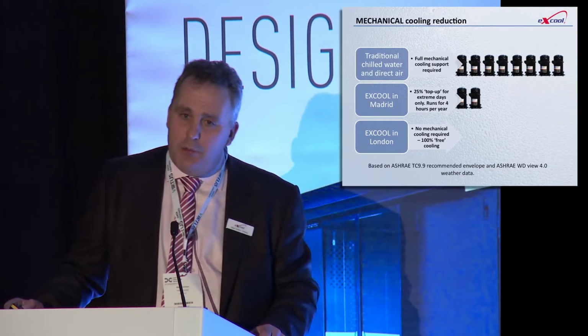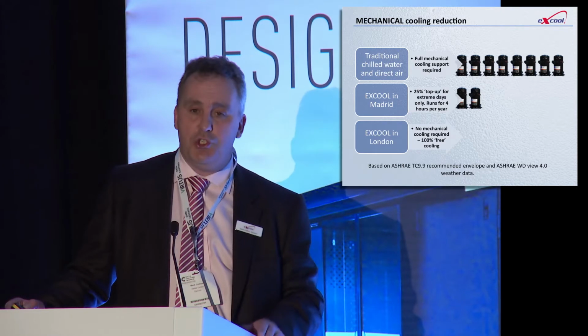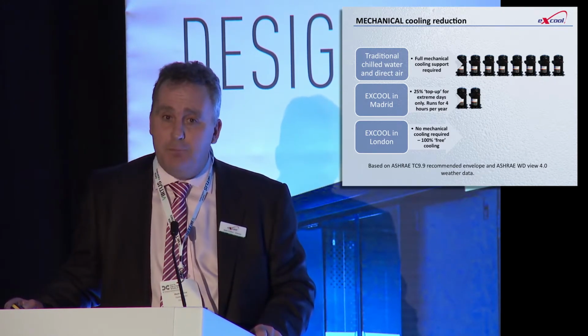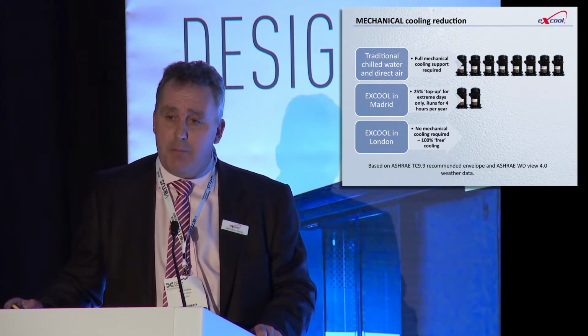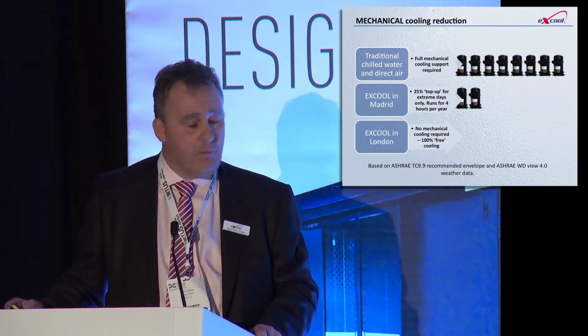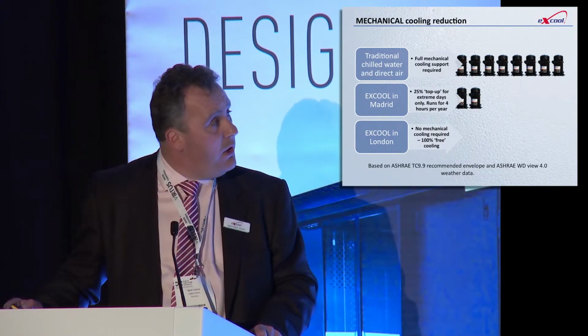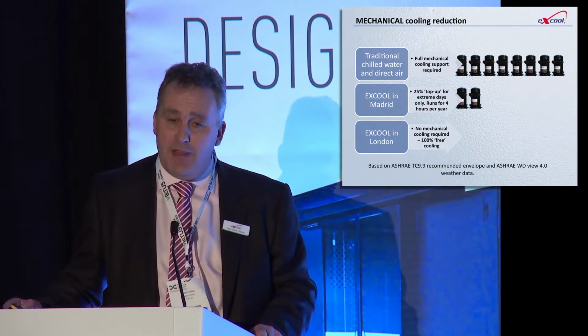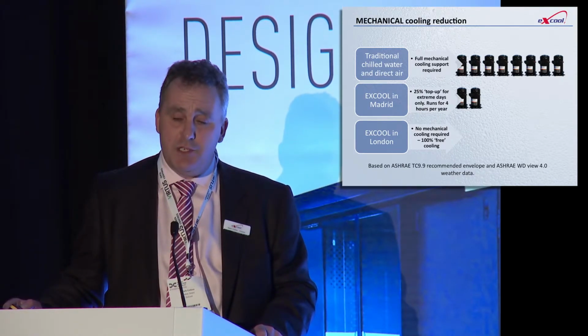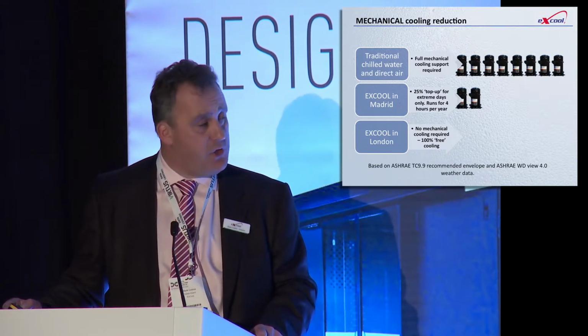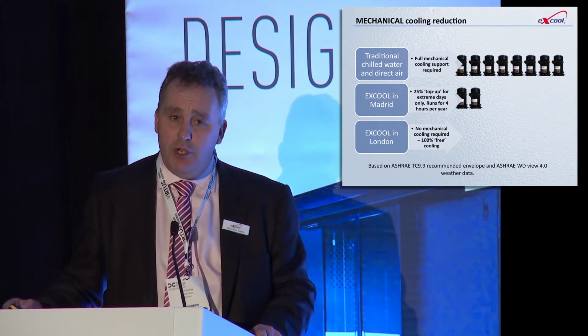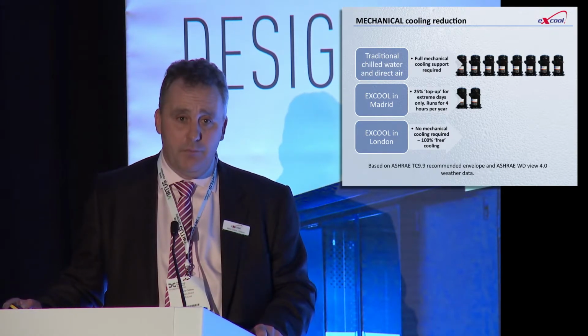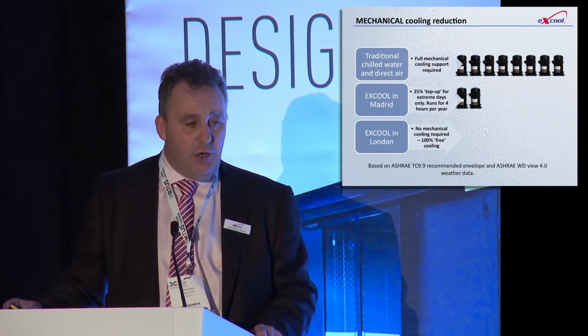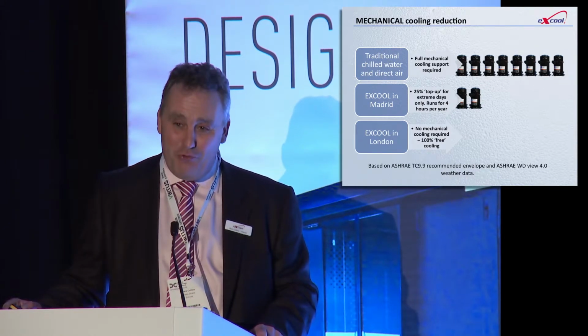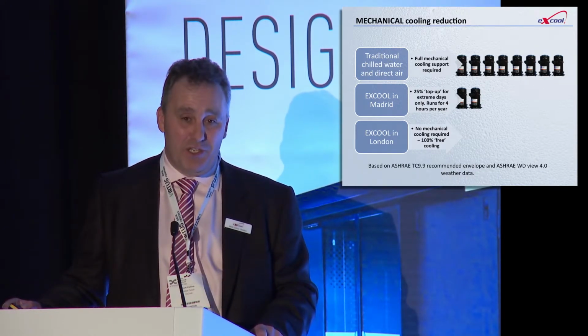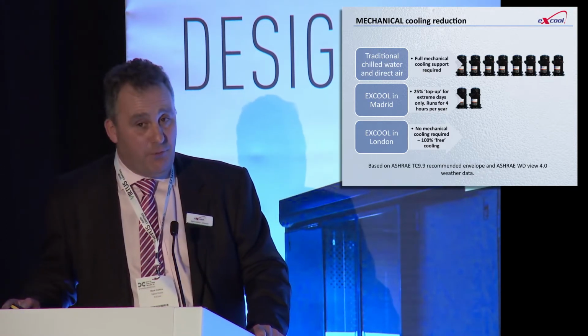So this illustrates what I'm trying to get across: if you've got a traditional chilled water or direct air system, you're going to need a full mechanical cooling backup. If you're in Madrid, you're only going to need 25% top up, and that will only run for 4 hours of the year to maintain 27 degrees C as a peak temperature. In London, no mechanical cooling is required at all. So it's 100% free cooling, but it's 100% mechanical free cooling. I want to stress that. So it's compressor free cooling. There's no such thing as free cooling.